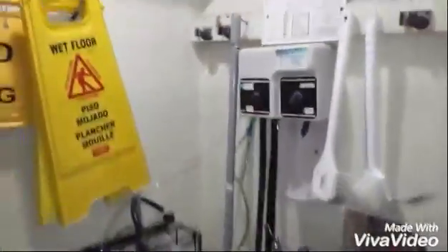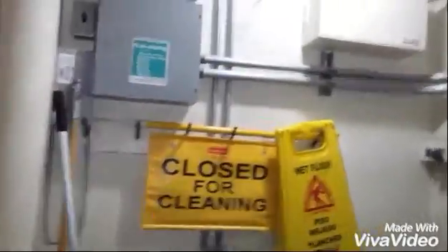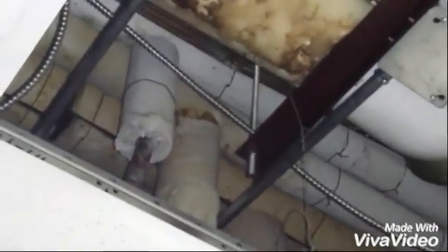This is in St. John's. I had to come and look at some banging steam lines, and then when I looked up in the ceiling, I found that white pipe there — the one that's whiter right there — with the open ends that look like cardboard. That is asbestos air cell insulation. Aside from loose insulation, that's the worst insulation you can have.